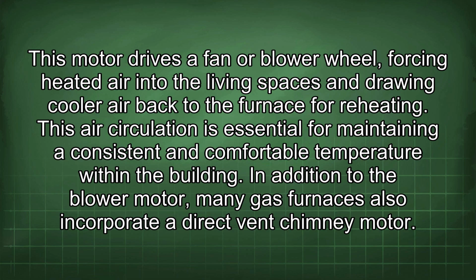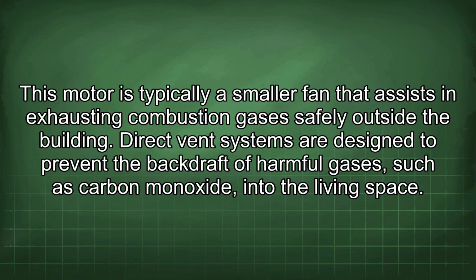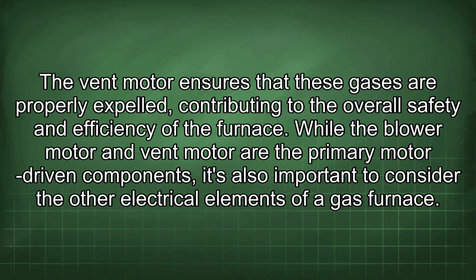In addition to the blower motor, many gas furnaces also incorporate a direct vent chimney motor. This motor is typically a smaller fan that assists in exhausting combustion gases safely outside the building. Direct vent systems are designed to prevent the backdraft of harmful gases such as carbon monoxide into the living space. The vent motor ensures that these gases are properly expelled, contributing to the overall safety and efficiency of the furnace.